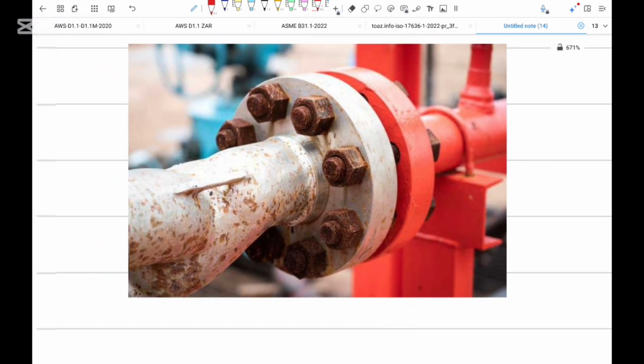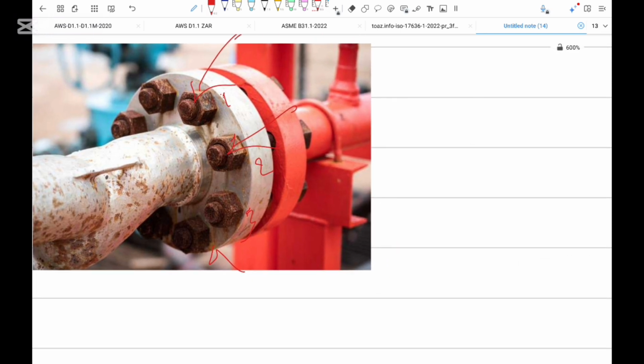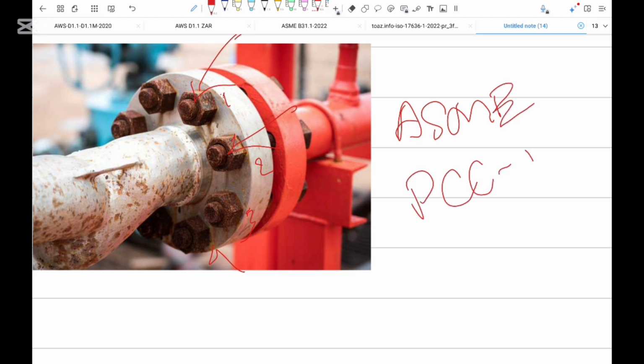Here you can see in this picture, we have already assembled the studs and then tightened the nuts. So stud number 1, 2, 3 and 4. All studs need to have the same tensile stress to prevent leakage. That's why we are required to check the elongation of the studs, and then we carry the data of elongation and calculate the tensile stress according to the formula mentioned in the ASME PCC-1. That is the general requirement for the stud bolt assembly for critical flanges.